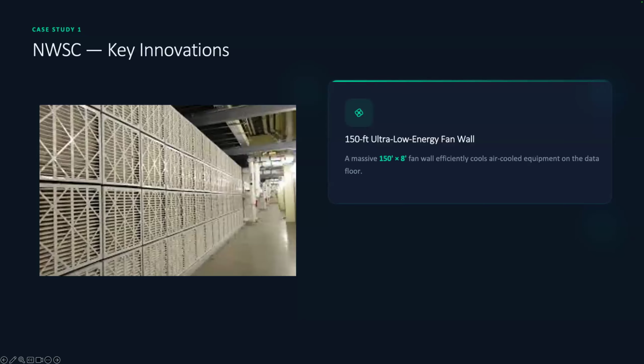I'm sorry, what's the question again? With going for the wide not fast, do you wind up with notable fronts in the full space? No. During commissioning, one of the interesting things, we really had to get our raised floor balance correct. So you have to have the right number of perf tiles to match that, let's just say 200,000 cubic feet a minute. We could levitate tiles, which was kind of cool. Kind of frightening, but there was enough pressure that we could levitate tiles if we had too much of the floor closed down.